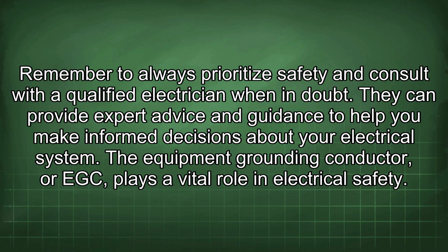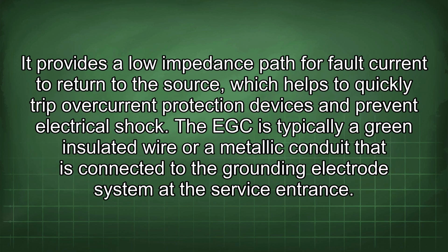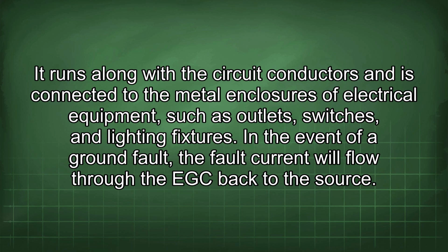The equipment grounding conductor, or EGC, plays a vital role in electrical safety. It provides a low impedance path for fault current to return to the source, which helps to quickly trip overcurrent protection devices and prevent electrical shock. The EGC is typically a green insulated wire or a metallic conduit that is connected to the grounding electrode system at the service entrance. It runs along with the circuit conductors and is connected to the metal enclosures of electrical equipment, such as outlets, switches, and lighting fixtures.